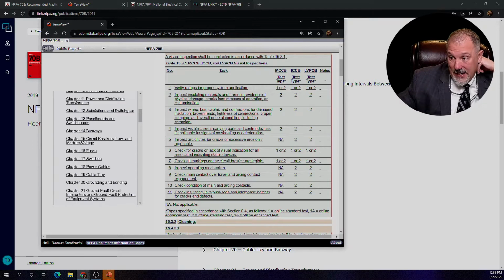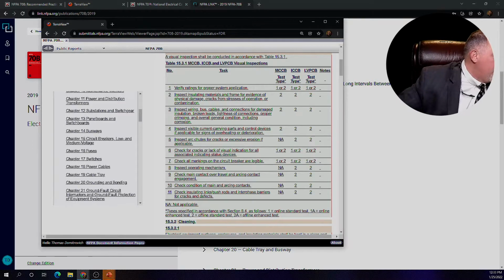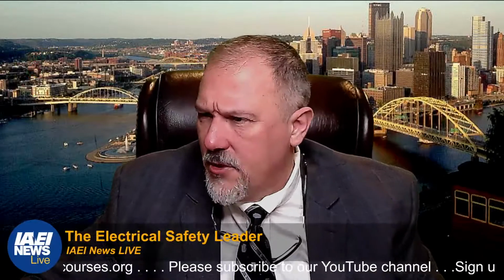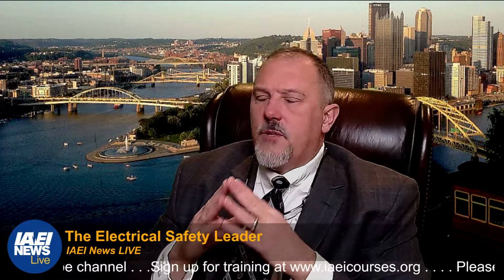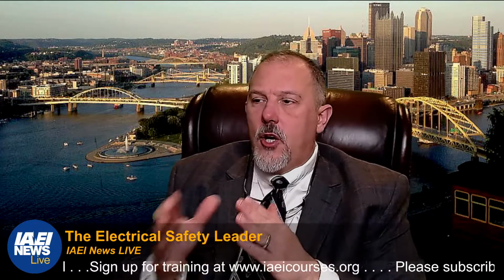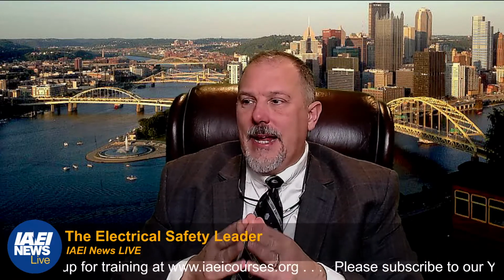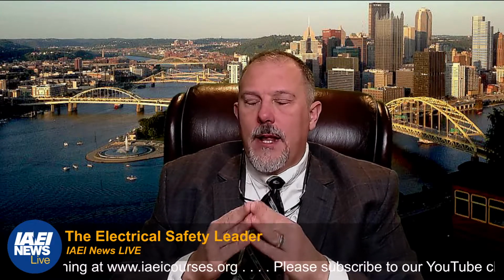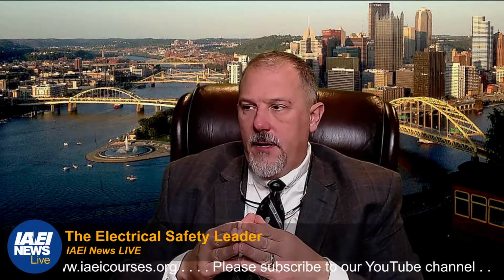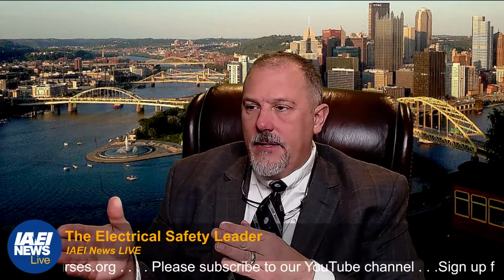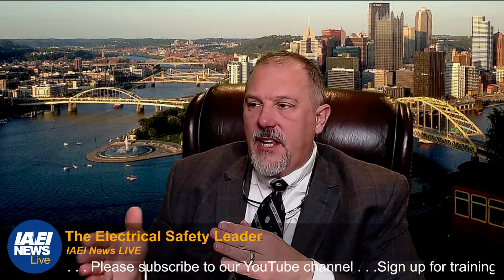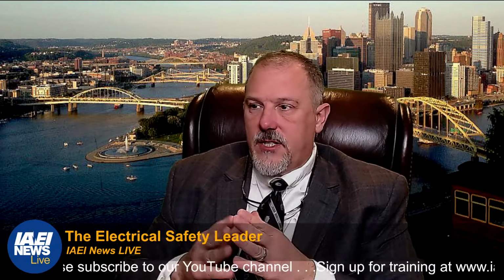Michael Hoffman says, as a service electrician, it is often very difficult to ascertain if electrical equipment has been properly maintained. Michael, you are absolutely right. We look at stickers on equipment, but here is my thought on this one, and I think I'll have to double check this, but in the general requirements, there is a section 5.2, electrical maintenance program. The equipment owner shall implement and document an overall electrical maintenance program that directs activity appropriate to the safety and operational risks.